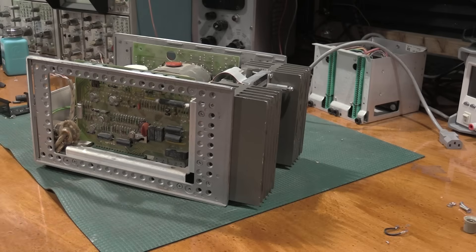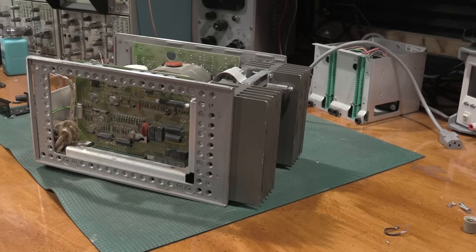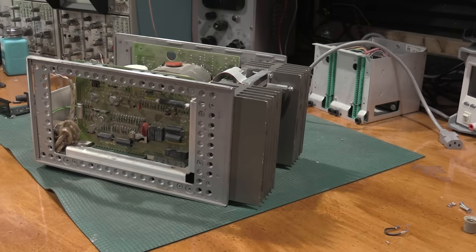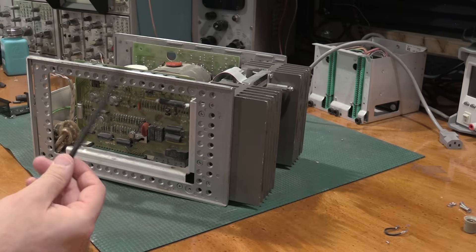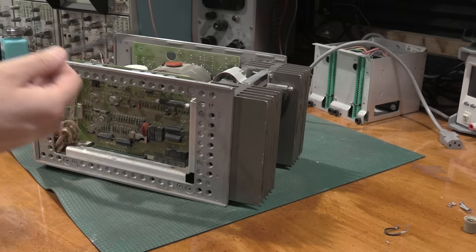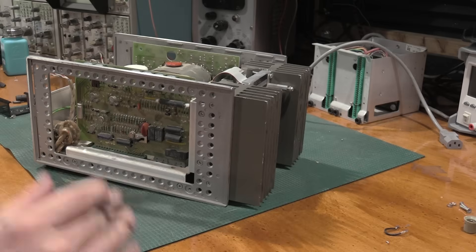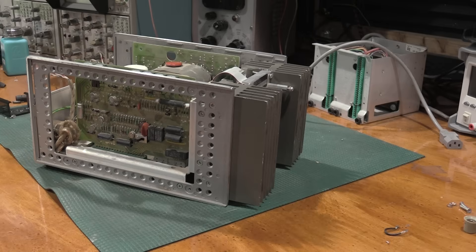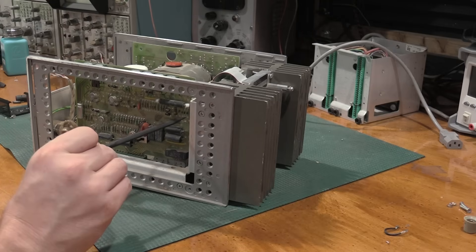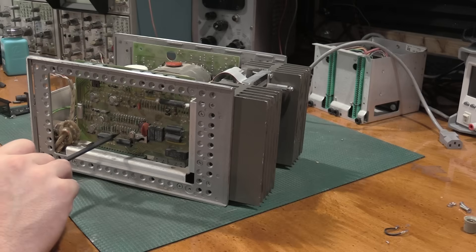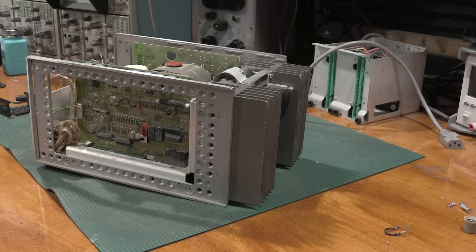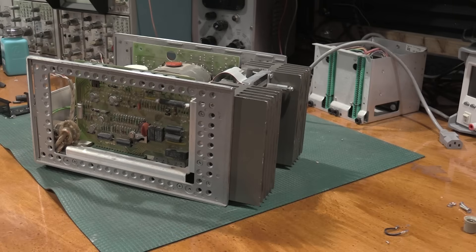Now we have some op amps here that are doing a lot of that switching, controlling, and compariting. And there's a troubleshooting step in the service manual that essentially says if the output's railed, which it is, and it's in constant current mode, there's really only two parts that go bad. There's a diode CR14 on the A2 board, and there's a transistor, Q6 on the power amplifier board. That is most likely the problem. I checked the power amplifier board. Everything's good. Check the, try to check this diode, and I'm really scratching my head because it says the diode's either open or shorted. And I pretty much just buzzed out every single diode on here, other than the zener that's right here, and every diode on the board checked fine. So I'm scratching my head going, okay, well, this is what it says to do. And everything's testing. So where do we go from here? Well, let's print out a schematic.